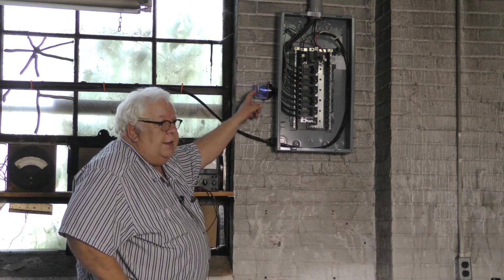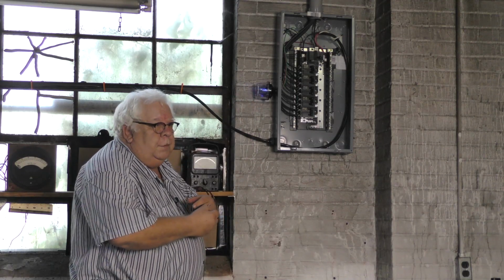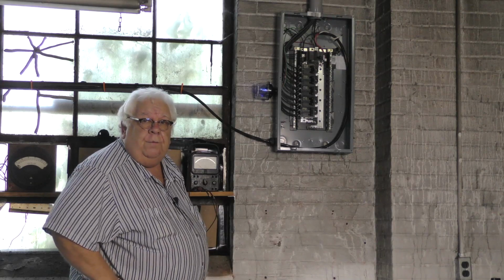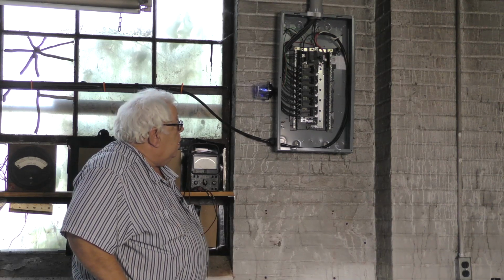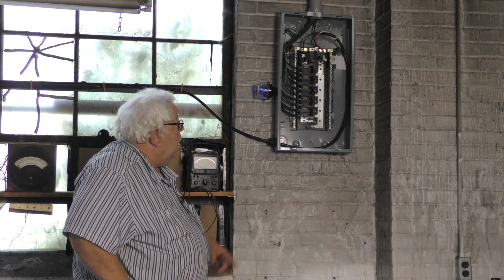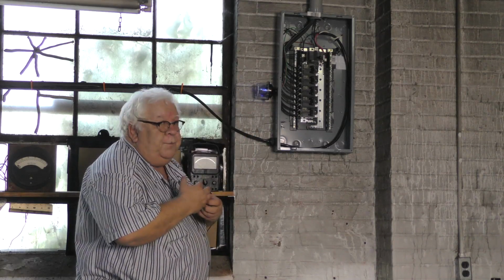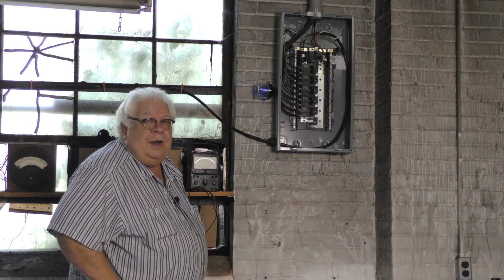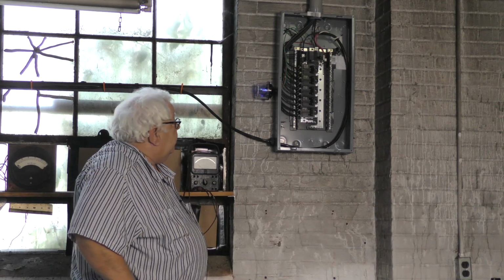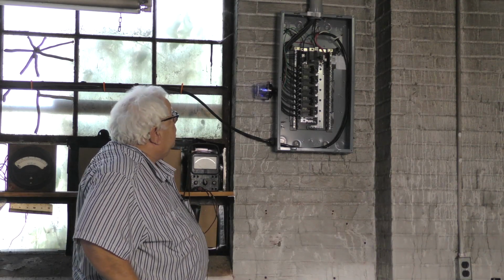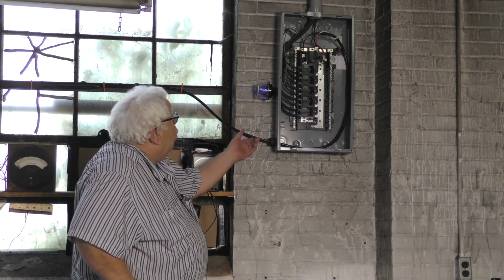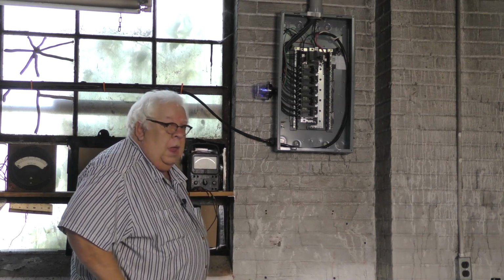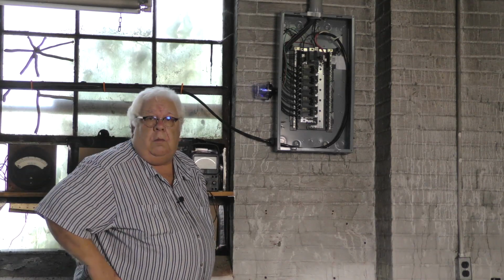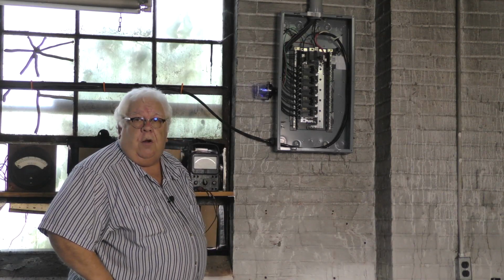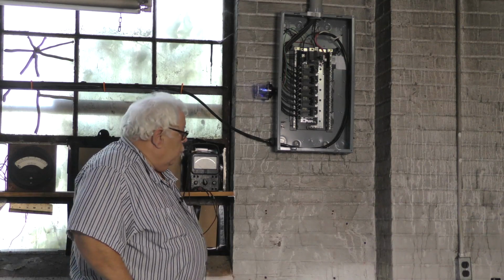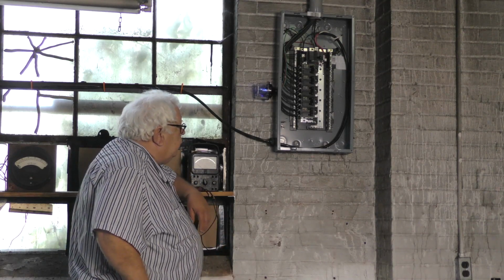And this is a Midnight Solar transient voltage suppressor that we put between the 2 phases on the master switch, L1 and L2, and ground. That should take out any spikes. Then we bring that out of the panel and over to a real loads panel for this part of the shop, and we'll take a look at that in a minute.